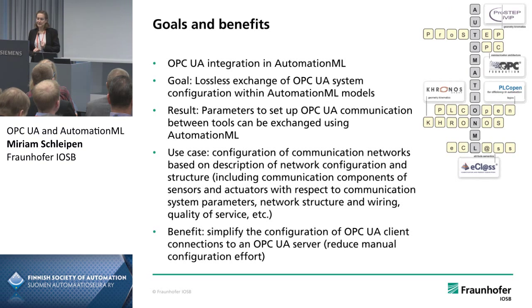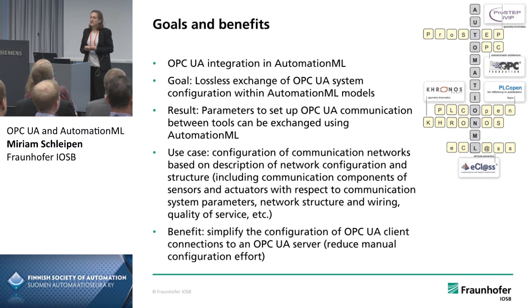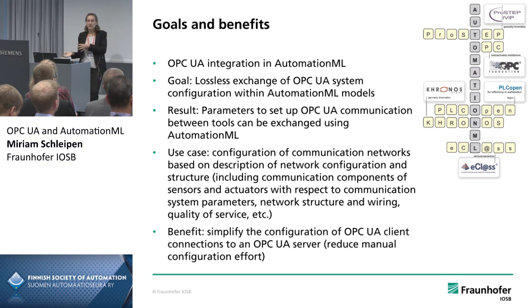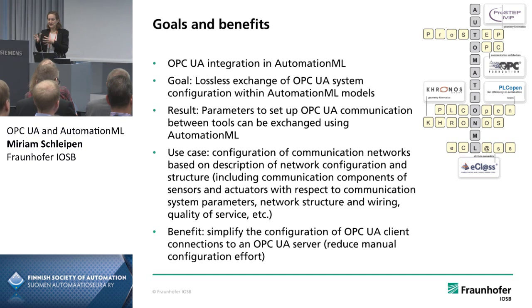On the other hand, it works the other way around too. OPC UA can be built up based on configuration data. To connect from an OPC UA client to a server, you need to know where the server is, what information it provides, and how to connect to it. This means that if you have your engineering models and describe your PLCs, PLC programs, and variables in AutomationML, you can also describe how to access these variables via OPC UA. You can integrate OPC UA configuration information into AutomationML models, so you have information for the online phase already available at the offline phase.